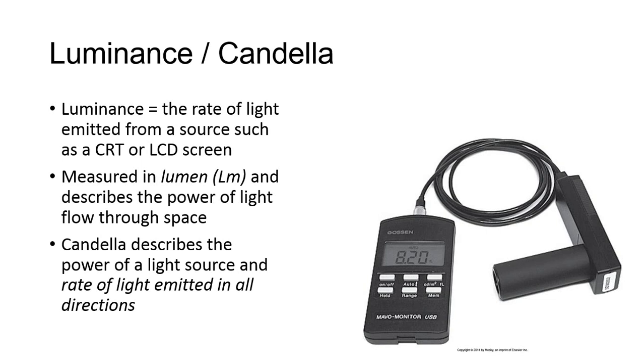Thankfully, we have equipment like the photometer, pictured here, to help us measure light flux. Most measure in units of lux, lumens, or candela per meter squared, and measurements should be documented once a year based on the specific manufacturer's instructions and acceptance limits.